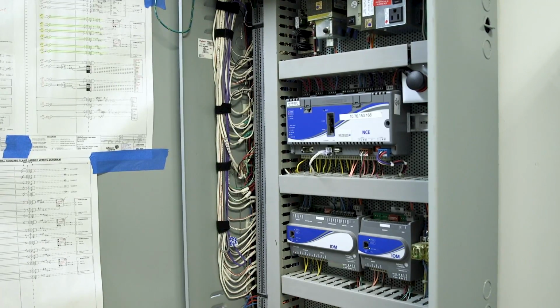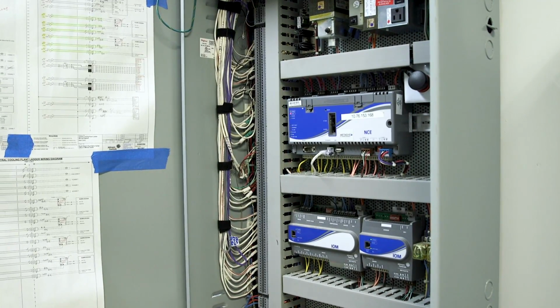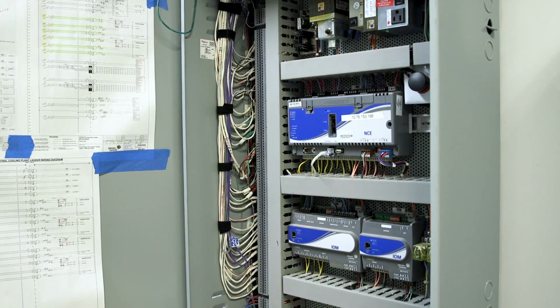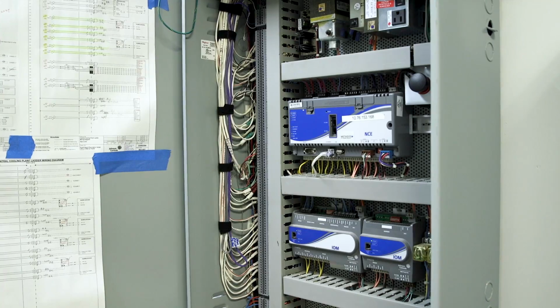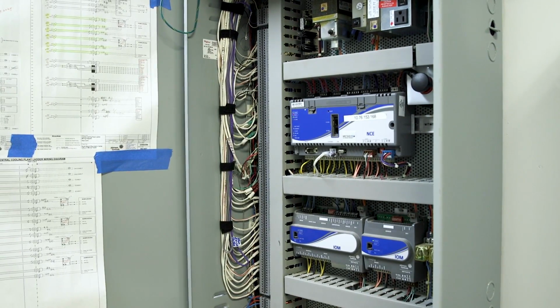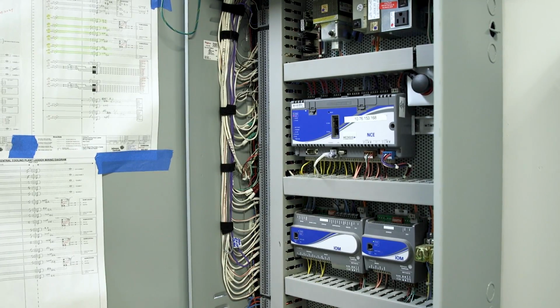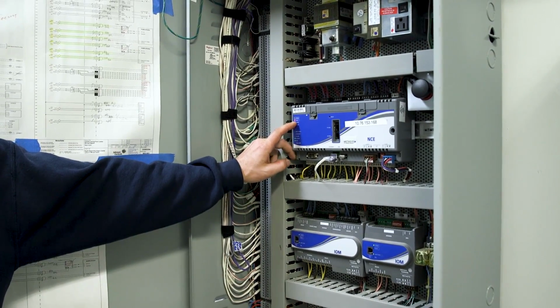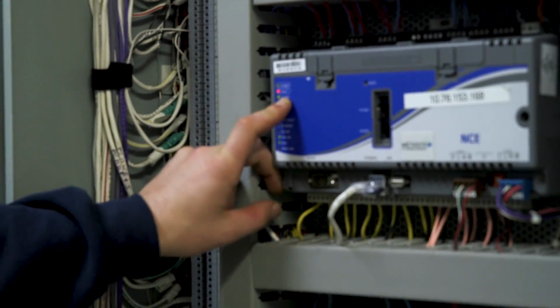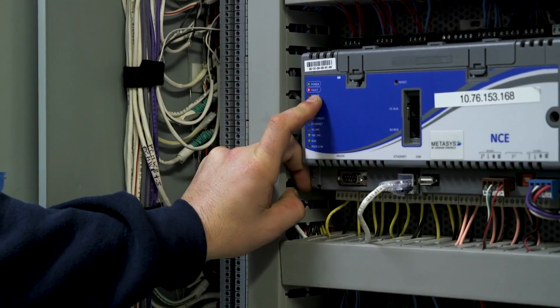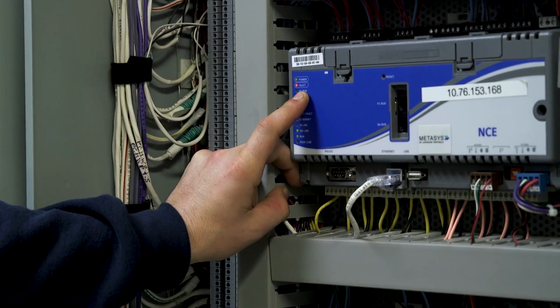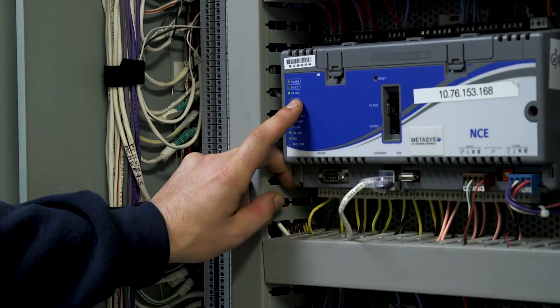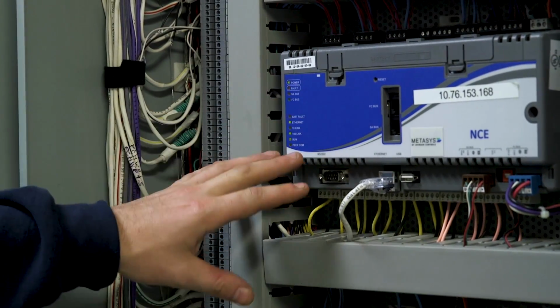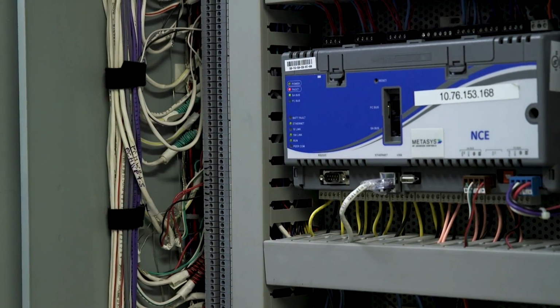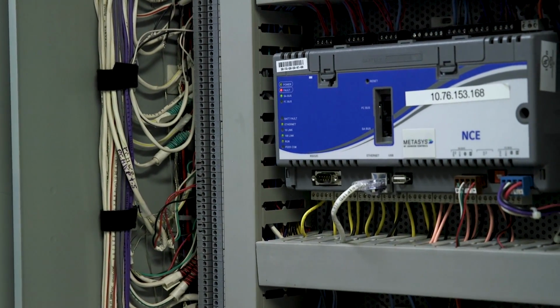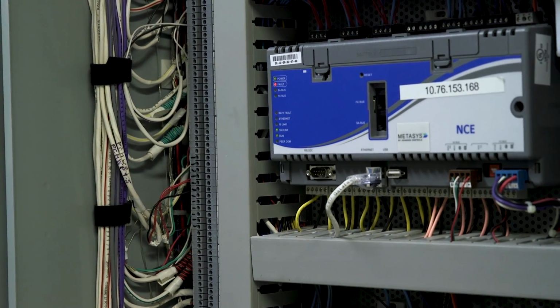One of the things I was saying downstairs was you could add up to 7 IOMs to one controller. The reason is you limit out the memory and the speed of the controller if you went past that. You know, you bog the whole system down. And as far as these, on the NCE you got these lights. The fault light, when you see a flashing fault light, it could be a bunch of different things. It could be internal board temp. It could be you're near the capacity of the memory in there. There's a couple different things. Just on this box itself? Oh no, for us to know that, we would have to go through the head ends, and it'll give you kind of a breakdown, like a diagnostic on it.